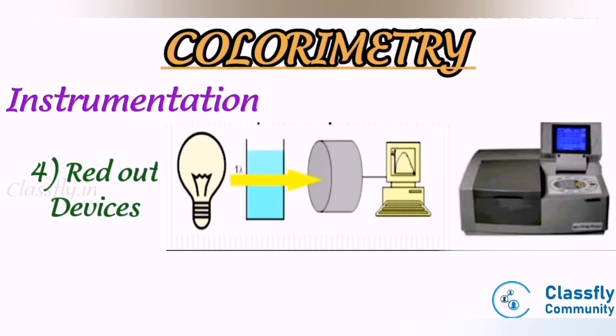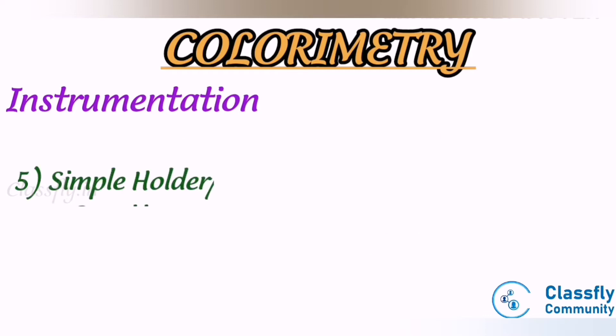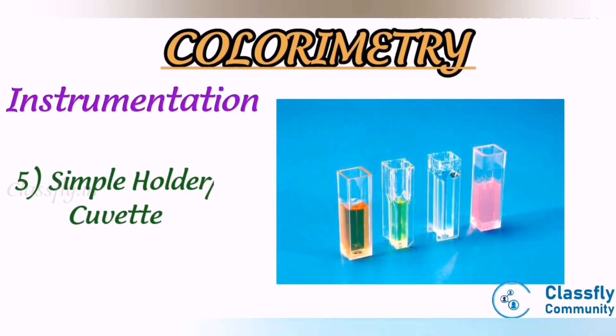Fourth, readout devices: the detector response can be measured by any of the following devices — galvanometer, meter, recorder, digital readout — and the signal may be transmitted to a computer or printout device. Fifth, sample holder or cuvette: cuvettes are rectangular, square, or circular cells made of optical glass for visible wavelengths, with capacity of 3 ml, 2 ml, or 1 ml.